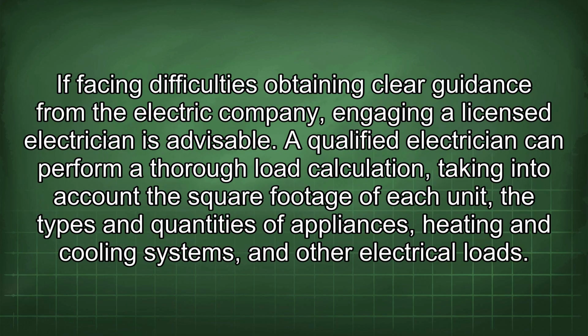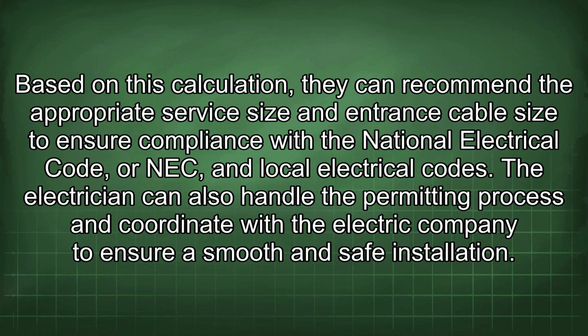If facing difficulties obtaining clear guidance from the electric company, engaging a licensed electrician is advisable. A qualified electrician can perform a thorough load calculation, taking into account the square footage of each unit, the types and quantities of appliances, heating and cooling systems, and other electrical loads. Based on this calculation, they can recommend the appropriate service size and entrance cable size to ensure compliance with the National Electrical Code, or NEC, and local electrical codes.